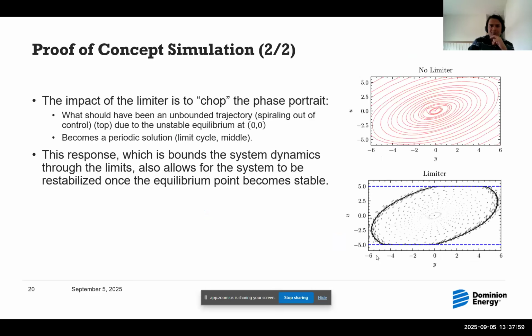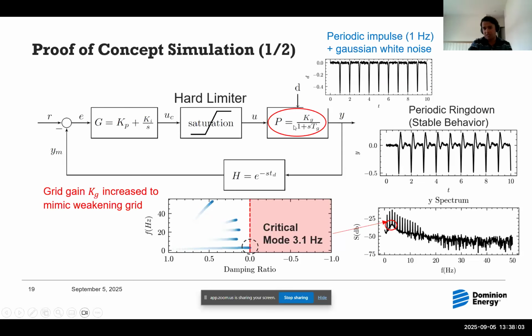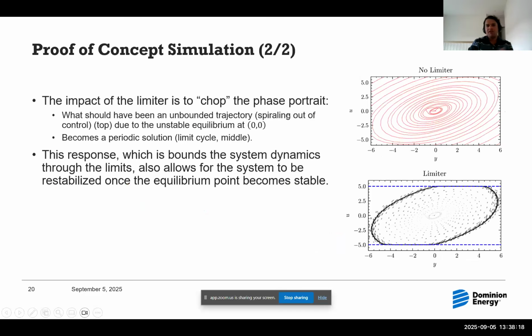Now what we'll do is make the controller unstable. We increase the gain of the grid, which mimics a more sensitive or weak grid. As we increase the gain of this grid block, we end up seeing oscillation, or the feedback control becoming unstable. Then we plot the phase portrait, in the u-y plane, looking at the trajectories with and without limiters. What you can see is that it's fairly easy to create a closed loop or periodic motion when you have hard limiters interacting with an unstable controller.